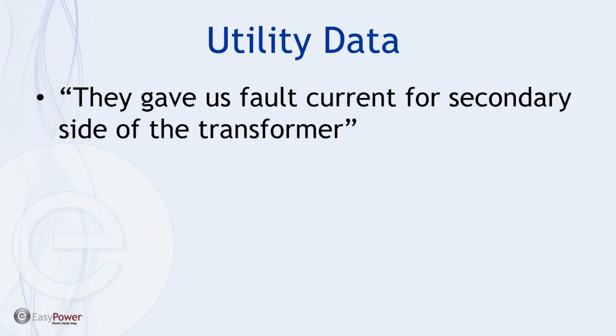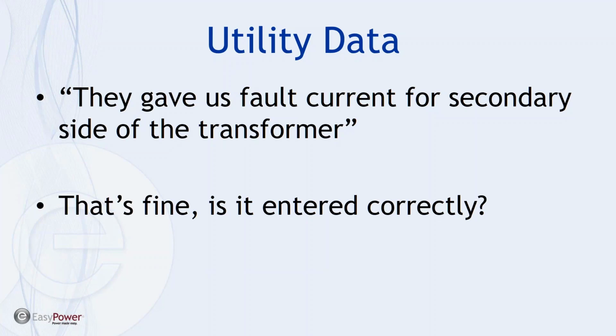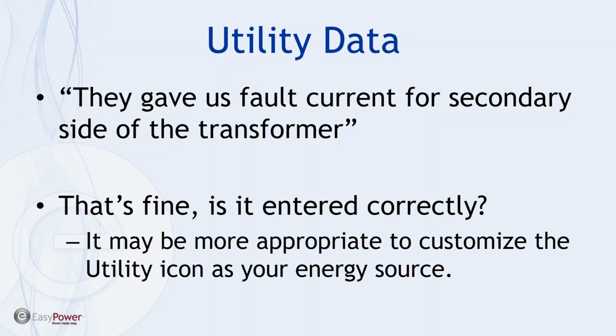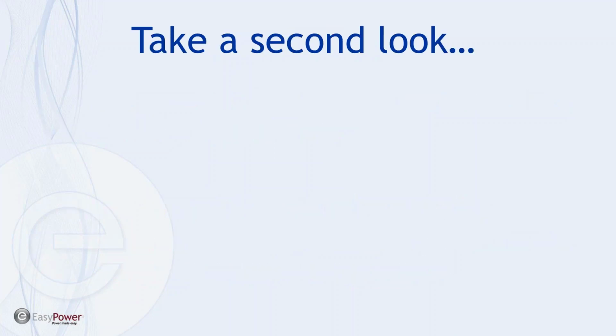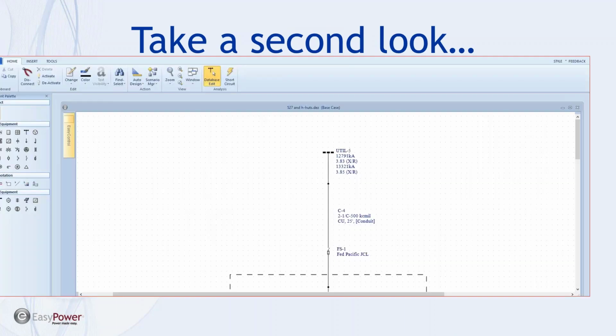Okay, so the statement was, well, they gave us the fault current for the secondary side of the transformer. What do I do with that? Well, it's fine if that's the way that data was presented to you by the utility company, but you need to make sure that you model it correctly. And a note to self, one way to deal with that is to not include the transformer, but to just modify, customize the utility icon as your energy source. And so you'll see as we get into this drawing, that's essentially what the customer did.